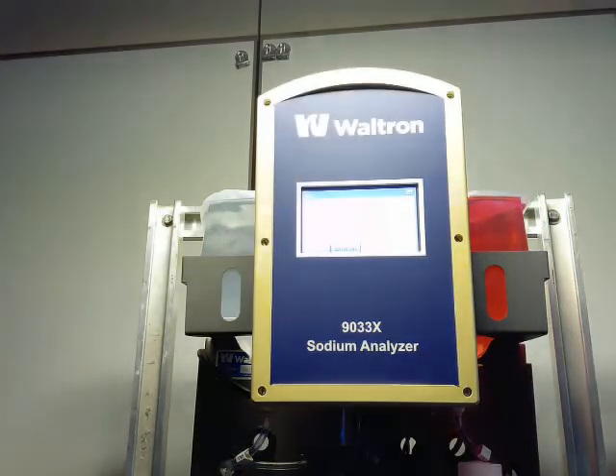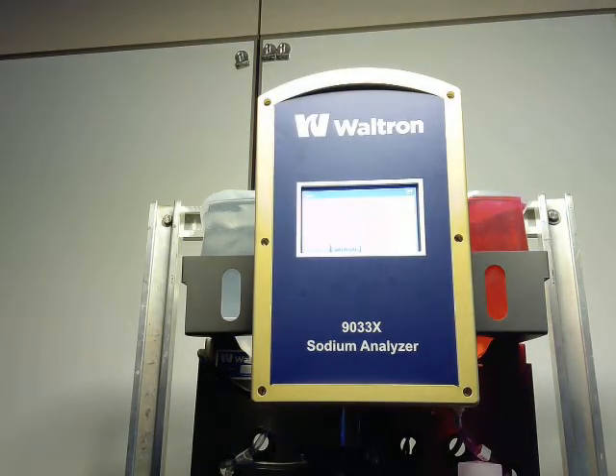If you do fail calibration, the analyzer will go back online using the last good cal factor or good cal slope. So that just means that if you failed cal because, say, you were out of a calibration standard, your number is probably pretty accurate still, but you cannot clear the cal failure alarm without passing a calibration. So you can't just continue to fail calibration, go to the screen, hit okay, I saw it, and then continue on your way. You do have to pass the cal to get that alarm to go away. But again, you still will go back to reading online with probably fairly good results, if it was just something due to lack of calibration standard.